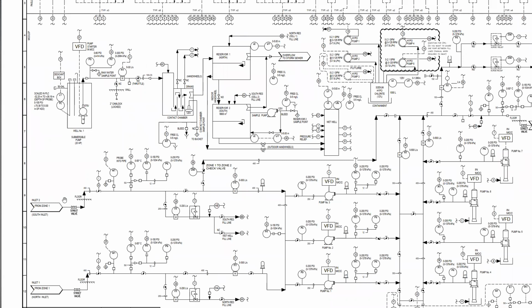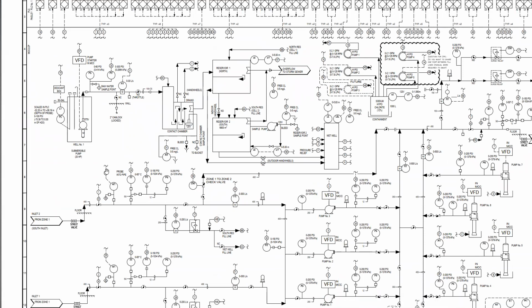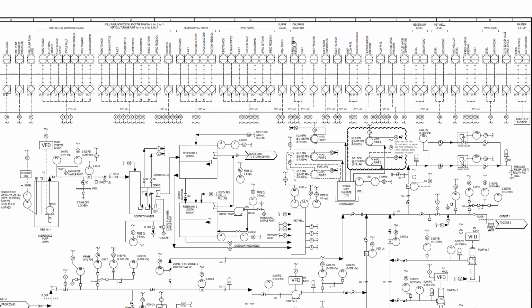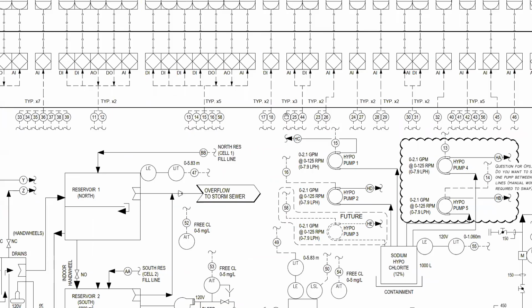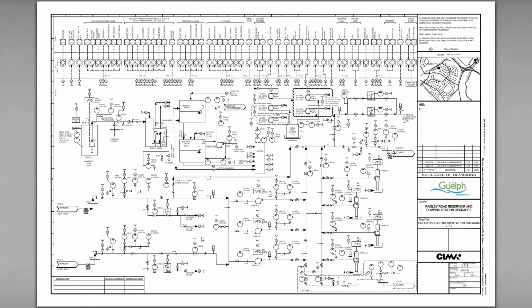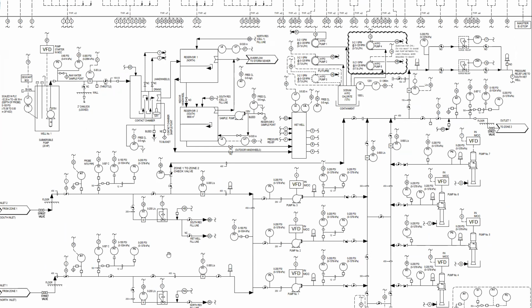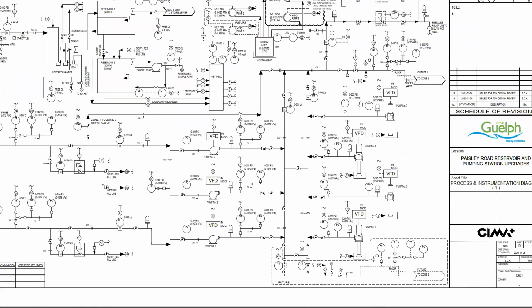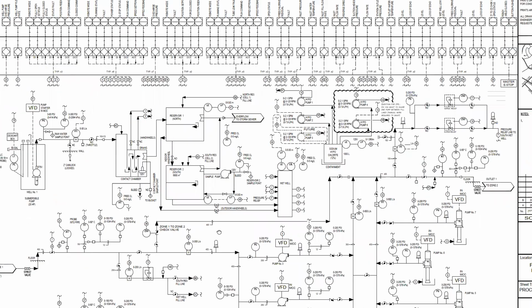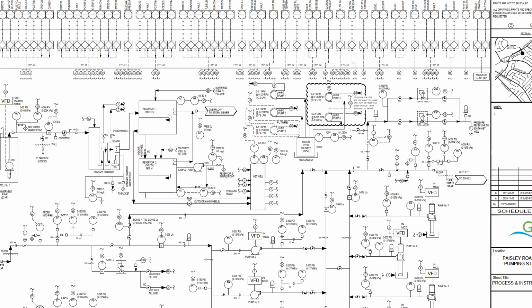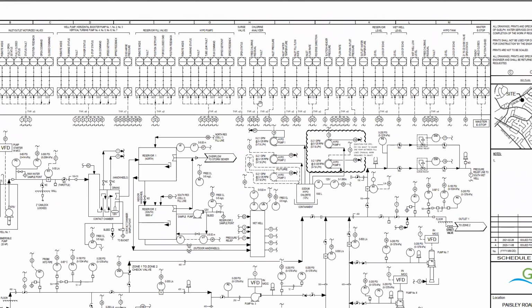Now we're using liberal use of those squigglies again that I was talking about. Zone 1 comes in, AIT1, 22 and a squiggly. Now we have to go play Where's Waldo and find 22. At 22, we have chlorine analyzers. It's a free chlorine residual, which is an AI, and a fault, which is a DI. And we have 3 of those. So if we were to look through this drawing and go 22, 25, 44, we've got 22, 25. I don't know where 44 is. Somewhere. So we multiply that. We got 2 times 3. There's 6 IO points, or 3 DI and 3 AI.